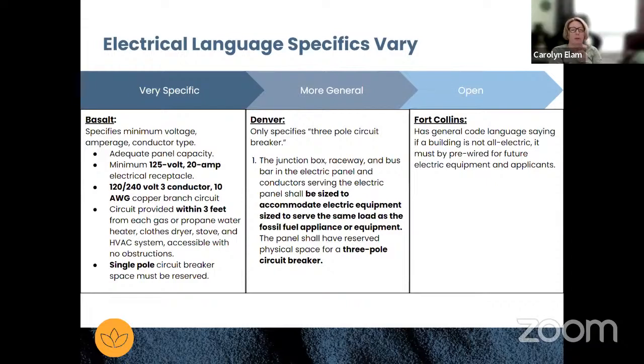Yeah, so let me clarify my question. You still have to design with that diversification in mind, right? So you'd be appropriately sizing the service for an all-electric building. My question is more: if you aren't putting in hot water heat but you are putting in circuits for hot water heat, don't you have to model the diversified heating loads to size that circuit? And wouldn't you then have to provide the capacity to serve that circuit, or not?